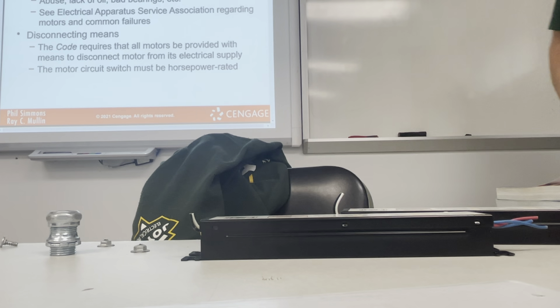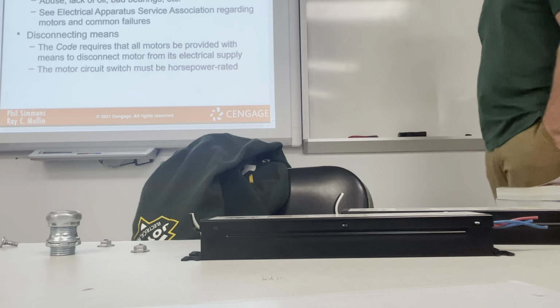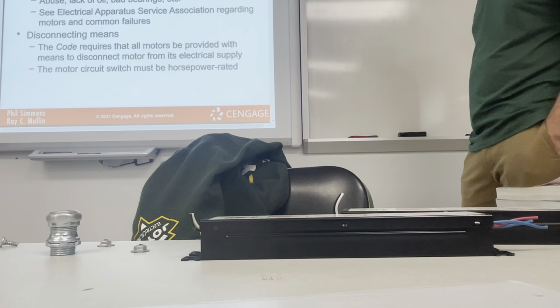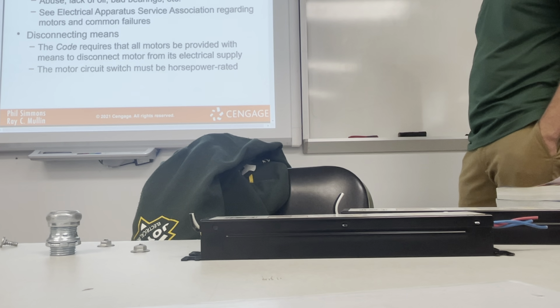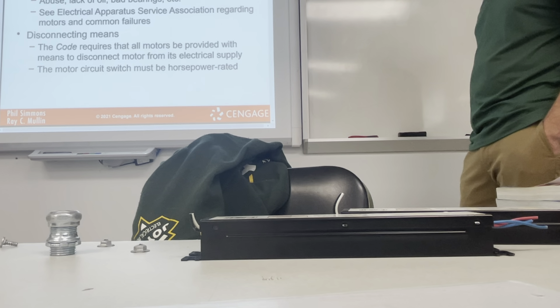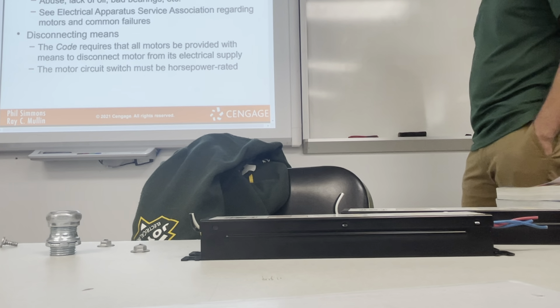The basics of motor circuit. Motor failures happen for many reasons: abuse, lack of oil, bad bearings, etc. See Electrical Apparatus Service Association regarding motors and common failures. Disconnecting means. The code requires that all motors be provided with means to disconnect motor from its electrical supply. The motor circuit switch must be horsepower rated.